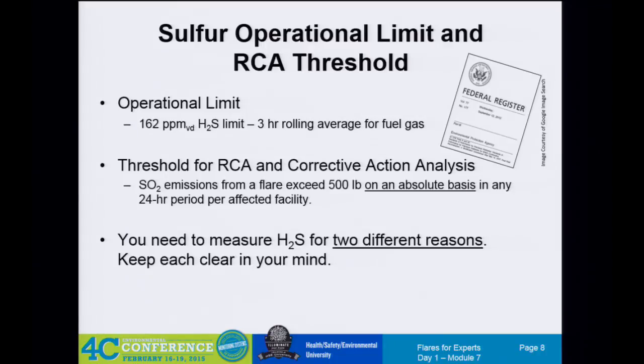One of the big things is the SO2 emissions limit of 500 pounds on an absolute basis. One thing to think about is if you have an interconnected flare system that's considered a single flare, so instead of 500 pounds going out one flare and 500 pounds going out another, if they're interconnected, it's 500 pounds total. So you can't think of them as different flares anymore, you have to think of it as one flare system.